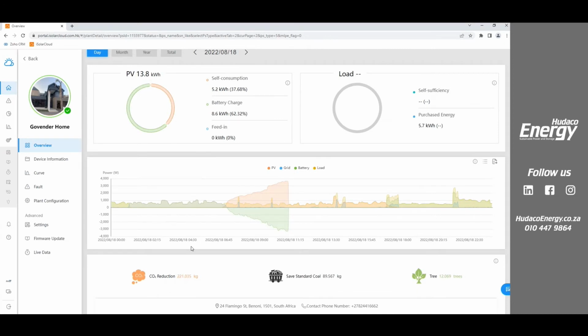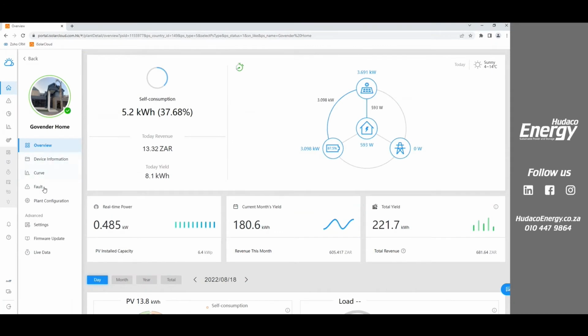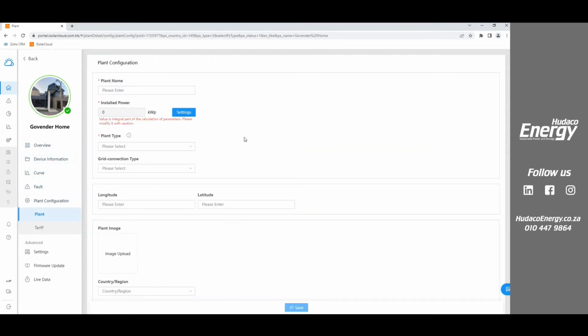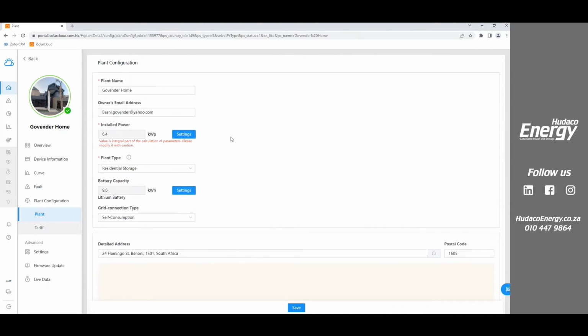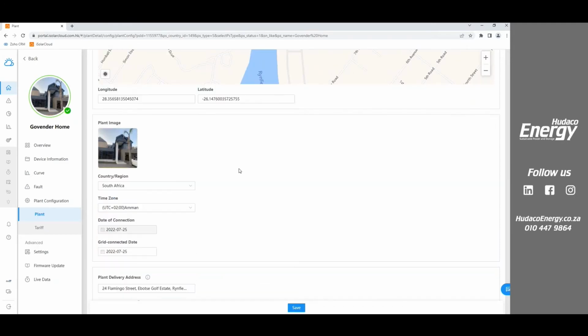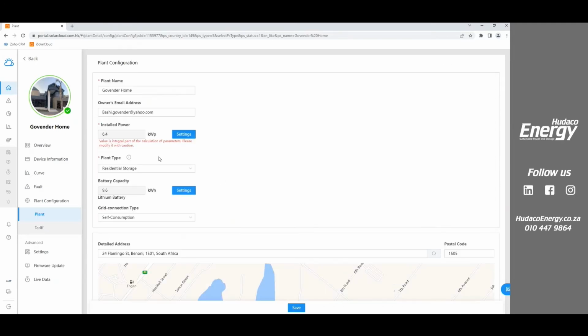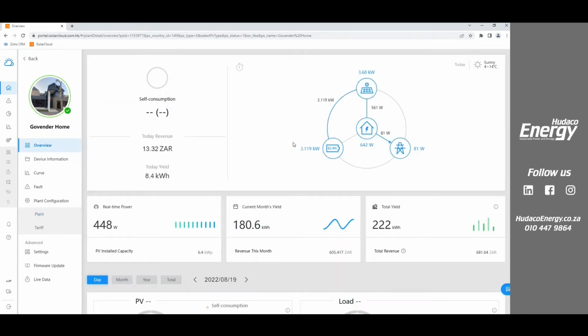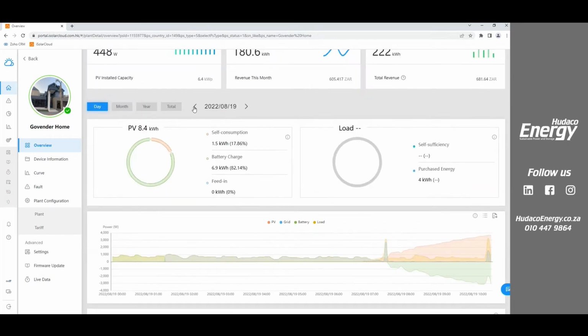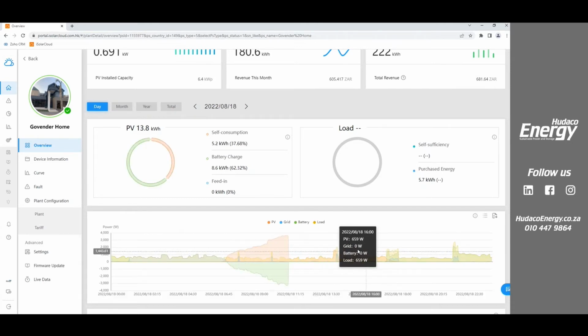So in terms of return on investment, this client has got 9.6 kilowatt hours of storage. They've got, I'll tell you how much they've actually got on site. It's just quickly loading up. They've got 6.4 kilowatt peak on site with 9.6 kilowatt hours of storage. They're in self-consumption mode. That's where they are. And we can see all of their information. So let's go back to yesterday again. What we're seeing is they are curtailing and they are wasting half of the energy that they're producing every day, right? So to do an ROI calculation becomes very, very difficult for us at this point until such time as they've optimized their system.